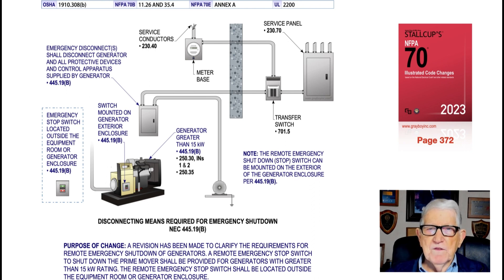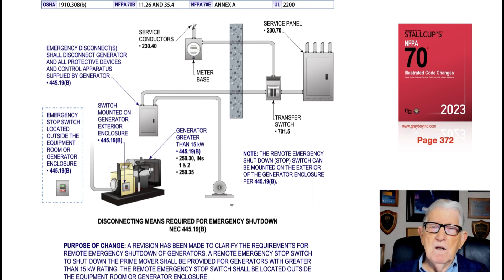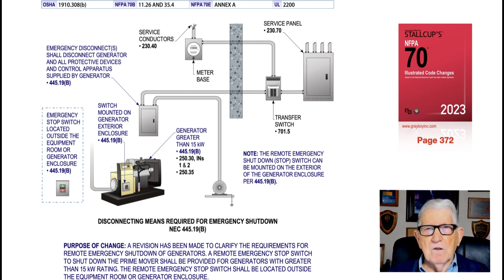When the generator has a rating greater than 15 kW, notice the arrow in the illustration pointing to the generator indicating it is greater than 15 kW. Key references to review include 445.19(B), 250.30 Informational Notes 1 and 2, and 250.35 when dealing with a permanently installed generator. The notes and call-outs in blue help you get a better handle on this type of installation.